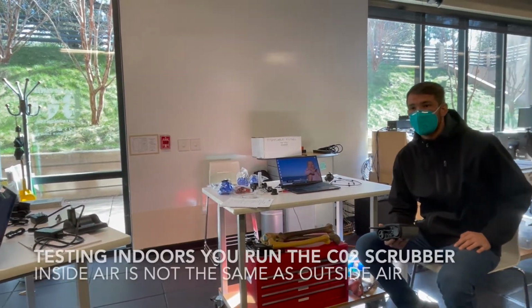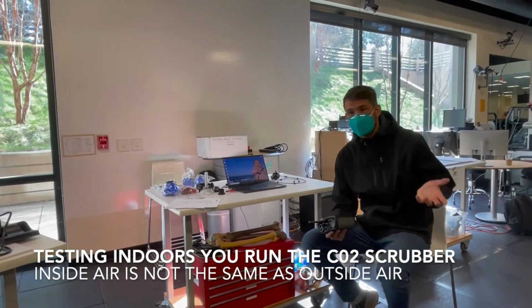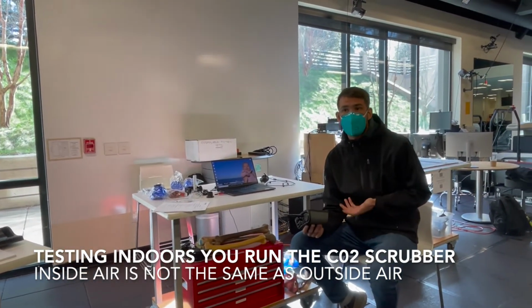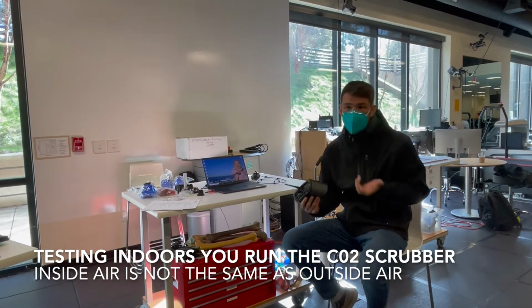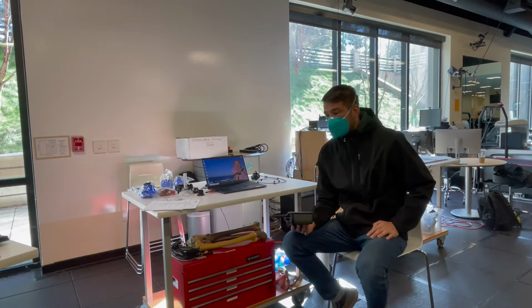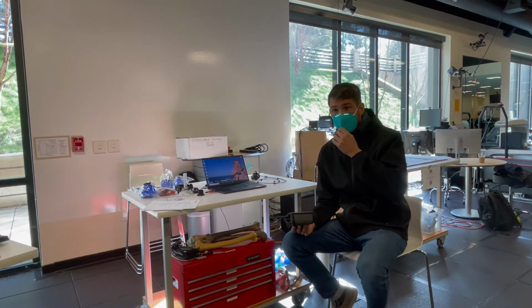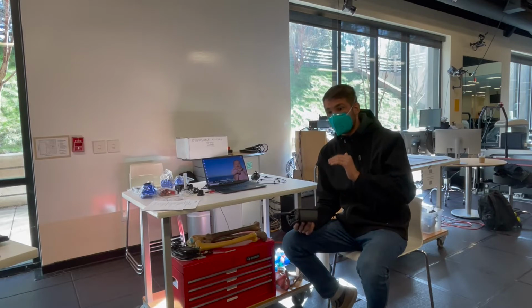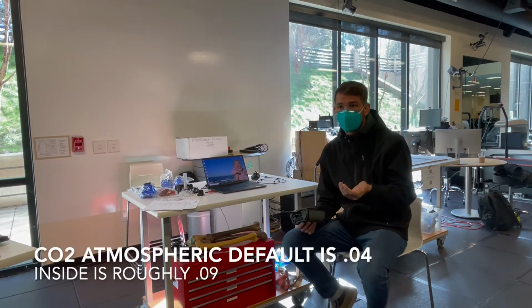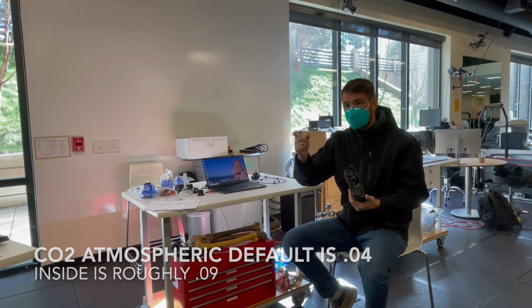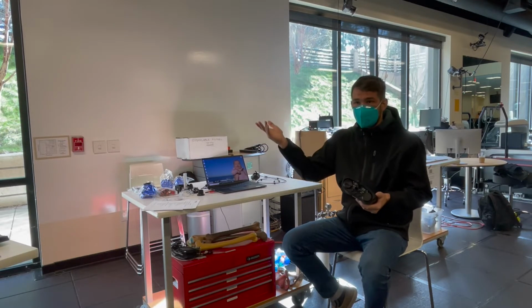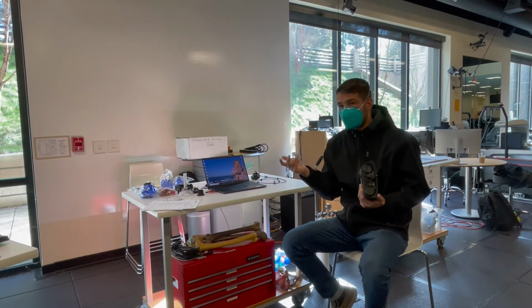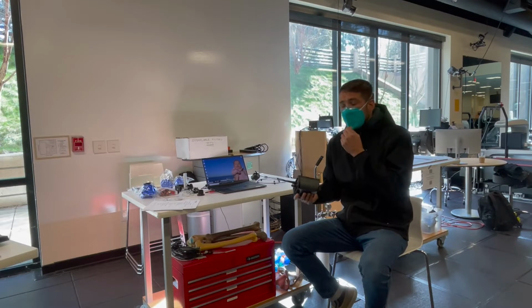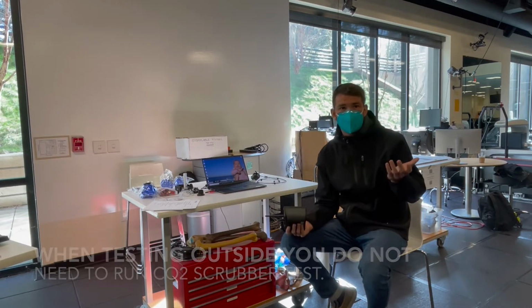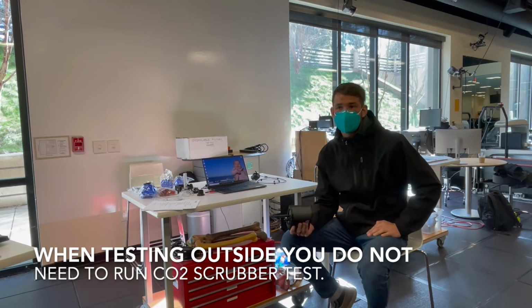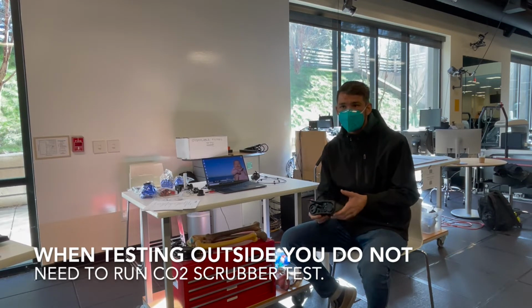CO2 levels in this room right now are not at atmospheric levels. I was measuring them just a little bit ago, and they're actually at 0.09. So you want to make sure that the system knows what the 0 point is, and then it can refer to its default, which is 0.04, and then it's going to know the difference, basically the analyzer's reading from atmospheric to the ambient CO2 levels within that room that you're in. And so if you're outside, we know that CO2 levels are always stable at 0.04, so you don't need to run the scrubber test.